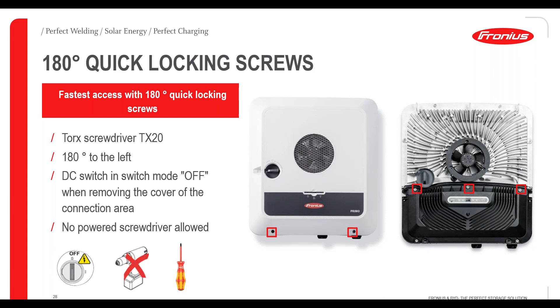Something else that is new on the Gen 24 is that we have 180 degree quick locking screws. So it's very easy to remove the front cover and the Datcom cover from the inverter. Because they are quick locking screws, you should not use a power tool to remove or put anything back, because it's easy to damage the screws with an electrical tool. Also, something that is good to know is that you have to put the DC switch to off in order to remove the front cover.